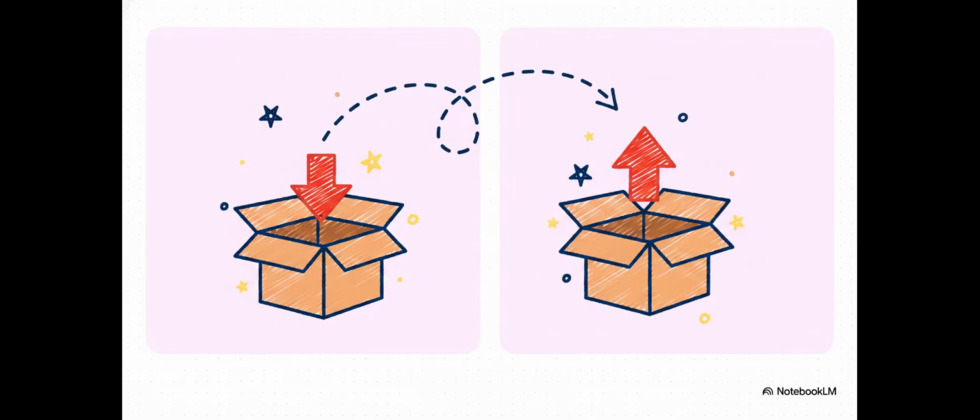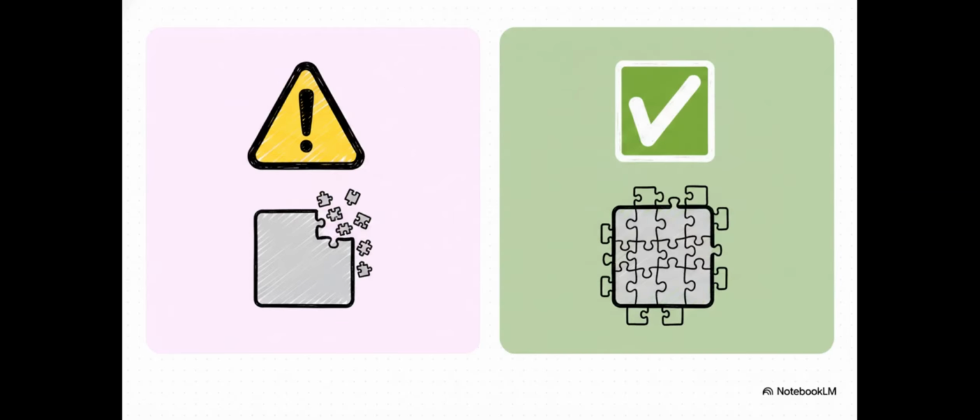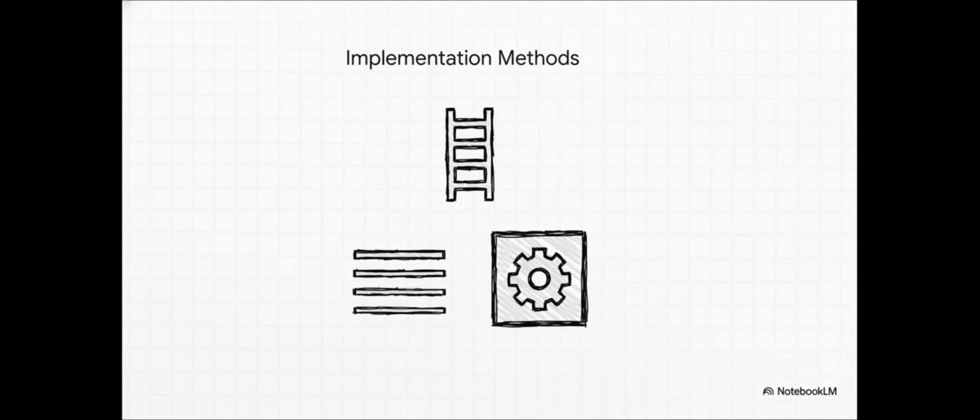Setup is a total breeze. Just pick your source tag to convert and a destination tag for the result. But watch out for this gotcha. Integer destinations drop decimal places. Always use a real tag for true precision. You aren't locked into one format either. Effortlessly use it across ladder logic, structured text, or embedded compute blocks.